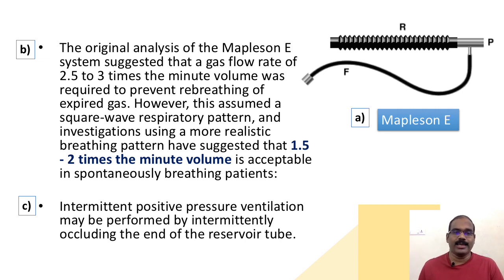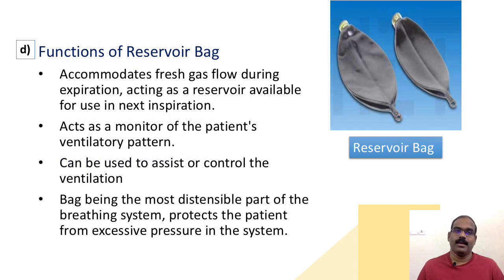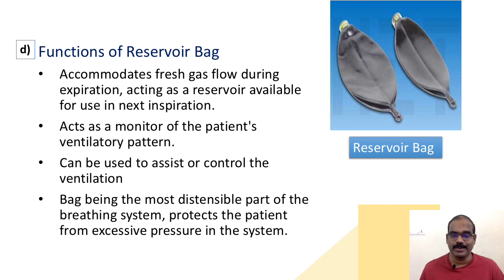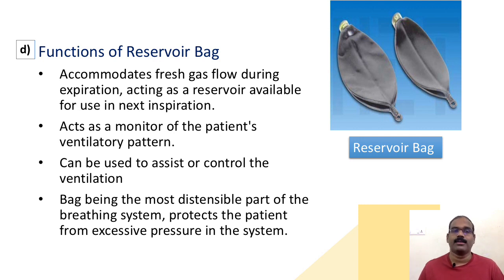For part three, how do you give intermittent positive pressure ventilation using Mapleson E (T-piece)? It can be performed by intermittently occluding the end of the reservoir tube. Part four is about the functions of the reservoir bag: it accommodates fresh gas flow during exhalation and acts as a reservoir for the next inspiration, especially to meet peak inspiratory flow demands. It monitors the patient's ventilatory status, can assist or control ventilation, and as the most distensible part of the breathing system, it protects the patient from excessive pressure.